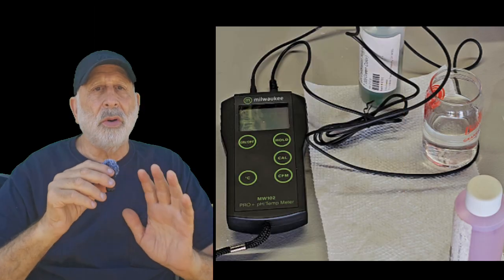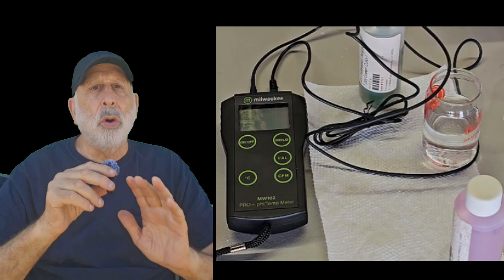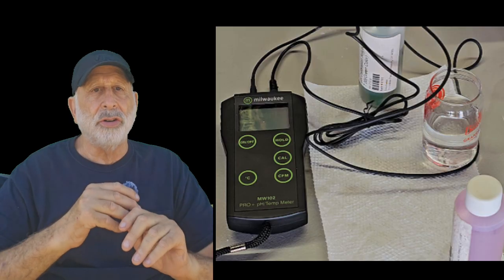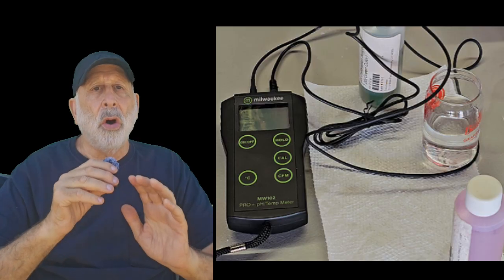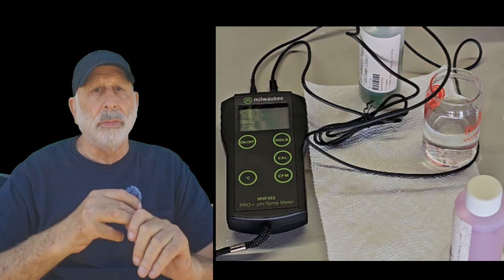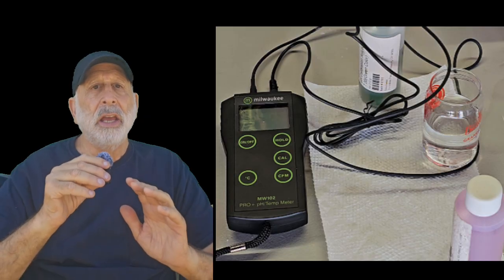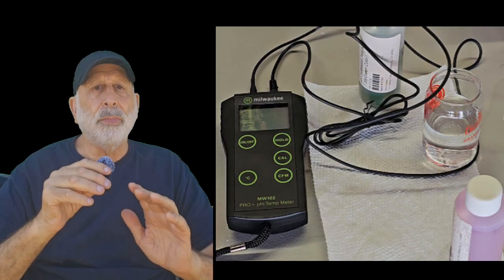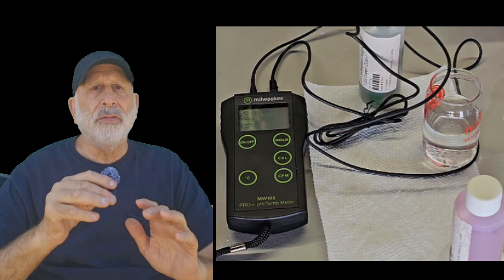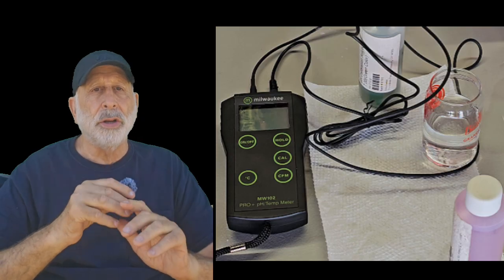So let's go back to summarize. 7.01 always comes first for a 2-point calibration. After that, the meter automatically expects 4.01. Only press Cal again if you want to switch that second point to 10.01. Always press Confirm to save each calibration point.